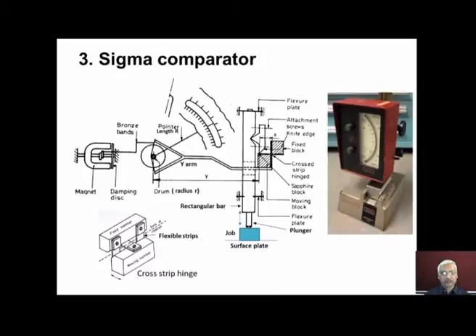Now let us discuss the sigma comparator. This photograph shows the sigma comparator. This is the sturdy base, and then we have a column on which the measuring head of the sigma comparator is mounted. We can adjust the height of this measuring unit by moving it up and down and then clamping it at the desired height. This vertical movement of the measuring unit is needed to adjust for workpieces of different heights. You can observe here a replaceable table. Depending upon the workpieces, we can replace these tables. And then we have to insert the workpieces between the surface of the table and the plunger.